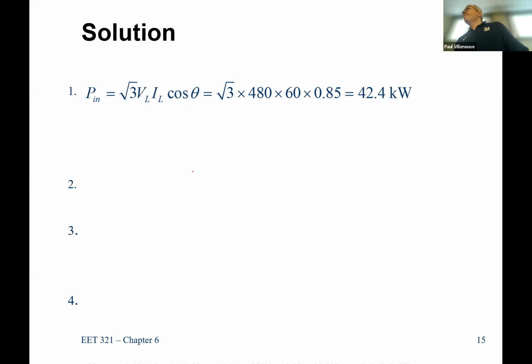Yes, it's still relevant whether it's delta or wye. Since I'm using V-line and I-line here, that accounts for whether it's delta or wye. If I were calculating equivalent circuits, I'd have to be careful about delta versus wye, but here I'm just calculating power losses and power in the machine, so all I need are 3-phase quantities—that's why I use V-line and I-line; they clean each other up, if you will.